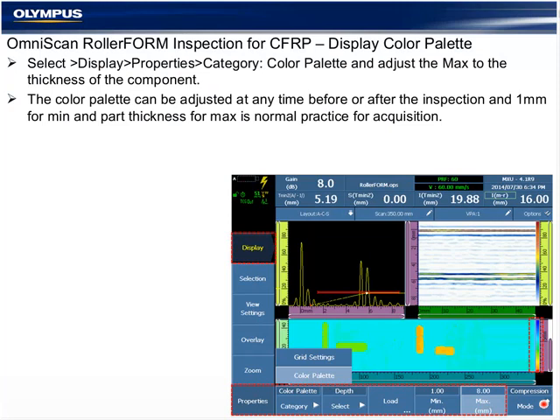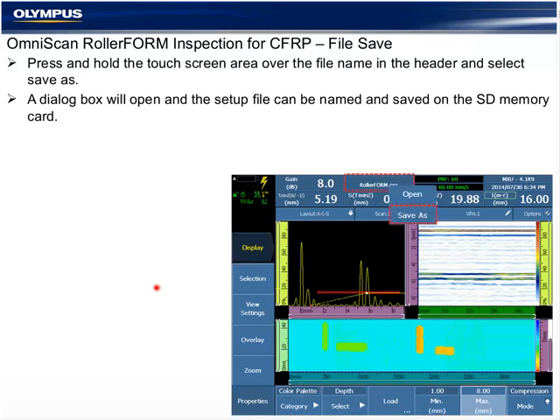And we can see here that the color pixel seen in the C-scan is a function of the arrival or time of flight of the leading edge signal in gate A, and its color is determined both by the scale that we see here under the UT gate thickness source, and the color palette distributed. As I change the color palette min-max, I will also see this contrast change inside the C-scan. The default values are normally a great place to start.